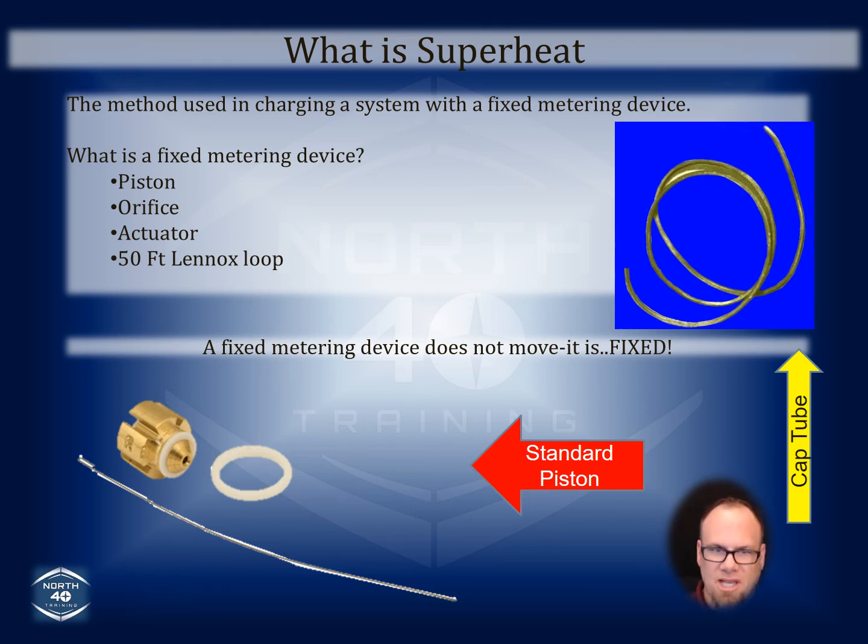Now on the opposite side of that, it'll turn back into water if it starts to cool down at 212 degrees, and it could very easily be 209 degrees, or it could be 70 degrees, like the water that's sitting on my desk. That is subcooled, right? It's cooled beyond the point that it took to change states from the steam back to the water. And that's really what we're talking about here. Superheat is adding heat beyond the change of states.